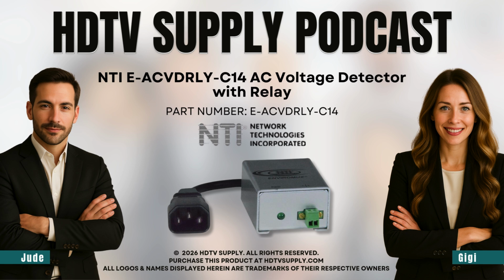Yeah, I found those thresholds really fascinating, this concept of hysteresis. So the relay closes when it senses voltage going above 60 VAC. Right. Power's on, the contact closes, everything's normal. But, and this is the important part, it won't open again until the voltage drops all the way down to 55 VAC, or even lower. And that 5-volt gap is completely intentional. It's designed specifically to stop the system from what we call flapping or chattering. So it's not just flipping back and forth with every tiny dip in power. Exactly. You get these minor, harmless fluctuations on the line, just electrical noise, and the last thing you want is a full-blown system alarm for that. Okay, so it prioritizes an accurate alert over an instantaneous one.